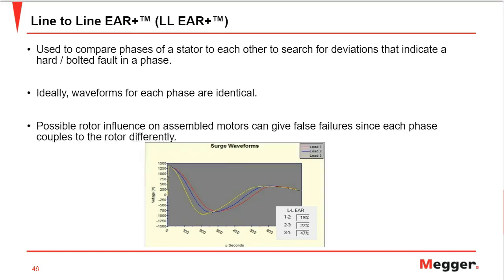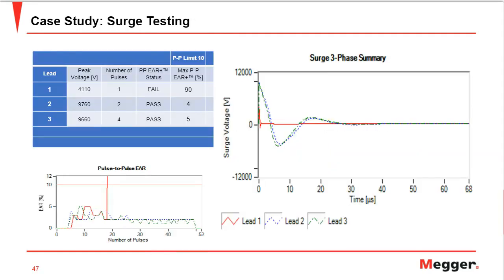We'll see a case study of a surge test. So let's move ahead and see the case study of a surge test which we conducted. As you can see on the screen, on lead one the motor failed at around 4,000 volts. The target test voltage was around 8,000 volts. So lead one clearly failed the test. You can see the pulse to pulse jumping and crossing the threshold.